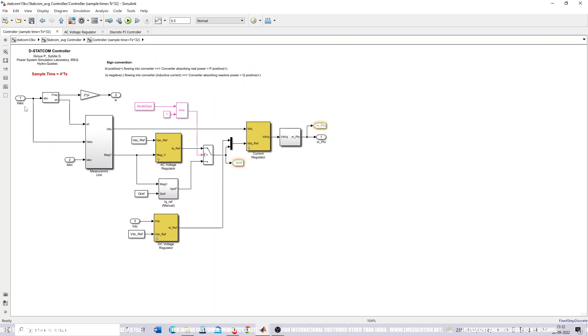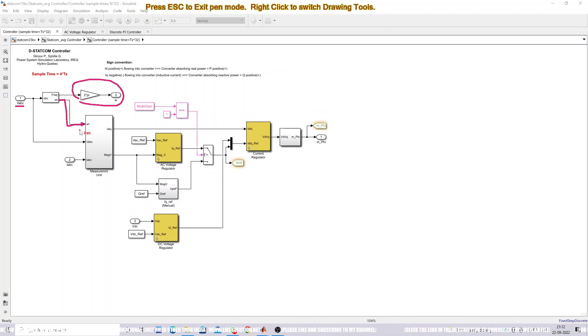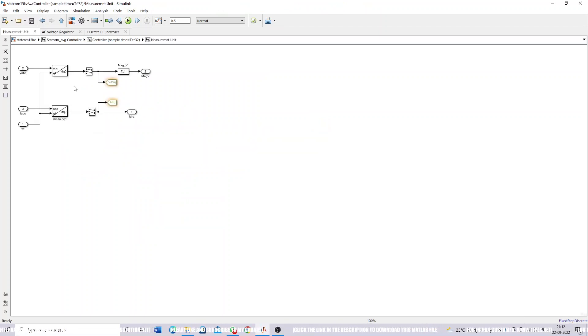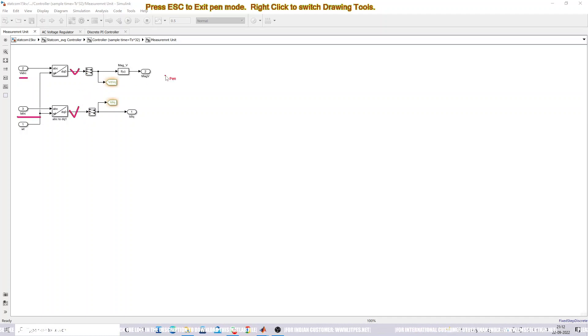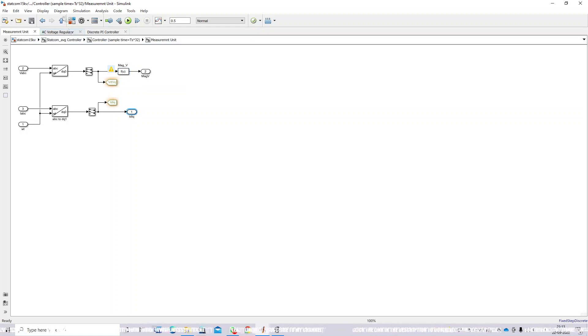From the three-phase voltage Vabc, we measure the angular frequency and phase angle with respect to time. Using the three-phase currents Iabc and voltages Vabc, we convert them into DQ quantities: ID, IQ, VD, and VQ. A function then computes the magnitude of the terminal voltage from VD and VQ, giving us the power system voltage magnitude. We also extract ID and IQ for the current controller.